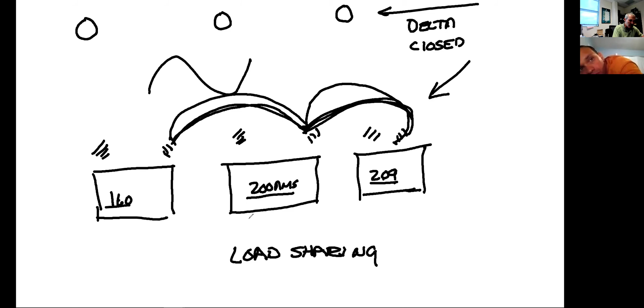The same thing happens in transmission. I don't want 900 amps on this phase, 600 on this one, and 700 on this one. What do I want? 800, 800, 800 -- I want it completely balanced so I get more efficiency out of my system. That's the benefit of closed delta.